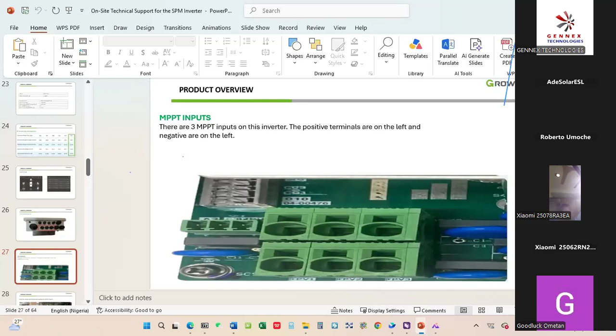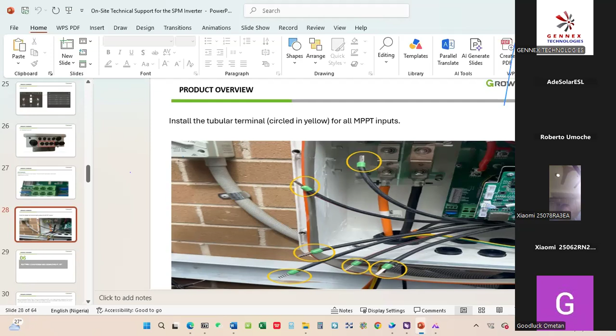Then you can install a tubular terminal when connecting your PV. What this does is that most times when you try to connect the stranded cables, they can't fit well into the terminals. When these cables do not fit well, the strands of one PV terminal can touch the strands of the second PV terminal, and it will cause a short circuit to the system. So always make sure you use a tubular terminal to avoid that error. When installing this panel, use a tubular terminal for all your PV terminations.